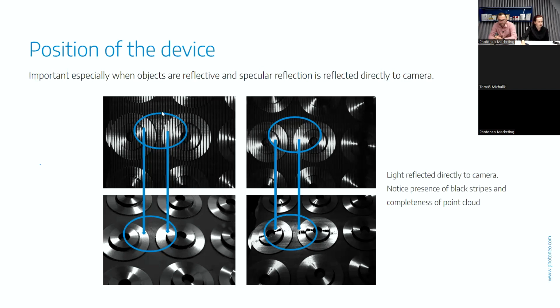So if you are positioning your device in a good way, it really comes down to distinguishing which parts are being illuminated by the structured light, by the pattern. If we are able to distinguish the white part from the black part, then we get a complete point cloud. But as we can see in this picture, the light bleeds through the black stripes. And that means that in those parts where there is bleeding of the light, the 3D point cloud cannot be reconstructed, because the pattern of the stripes that are emitted by the scanner is broken.